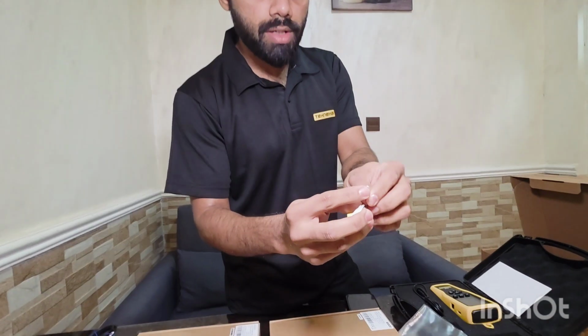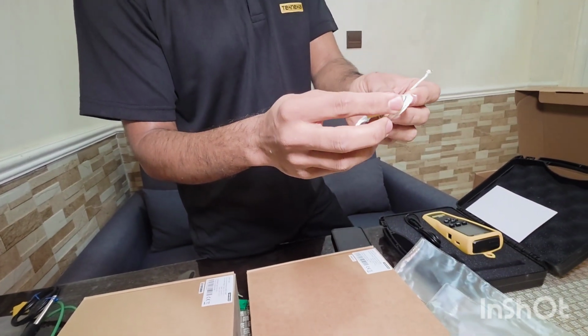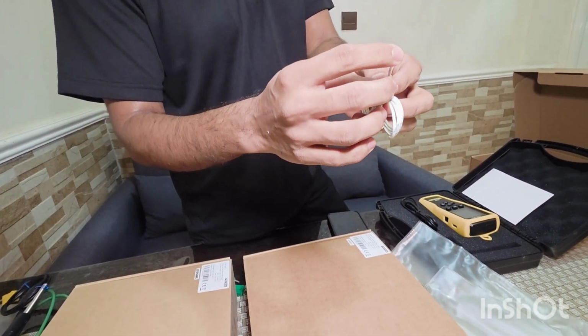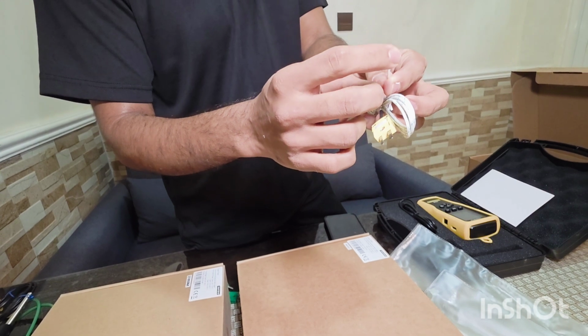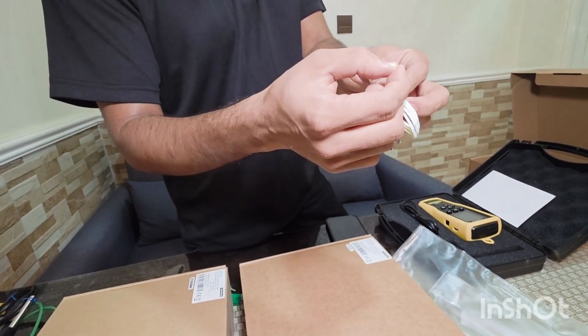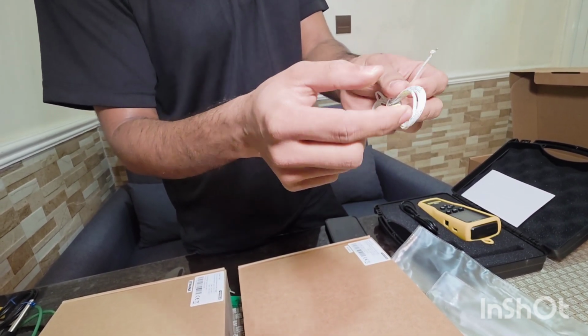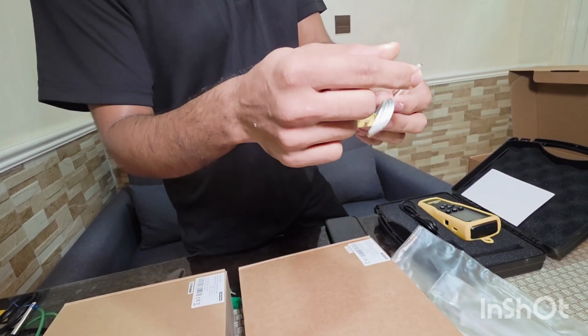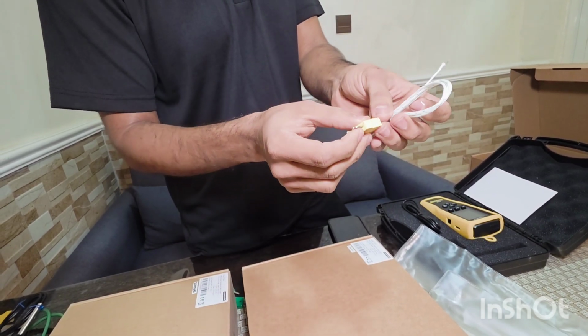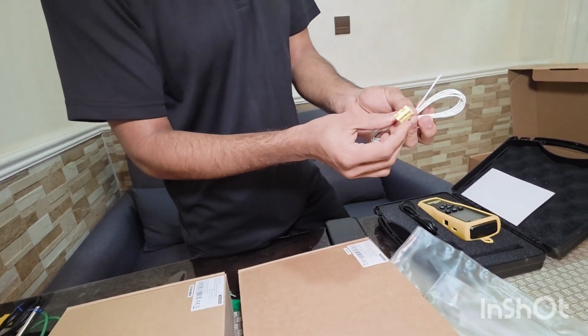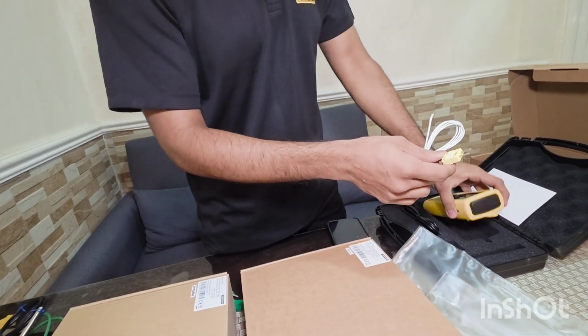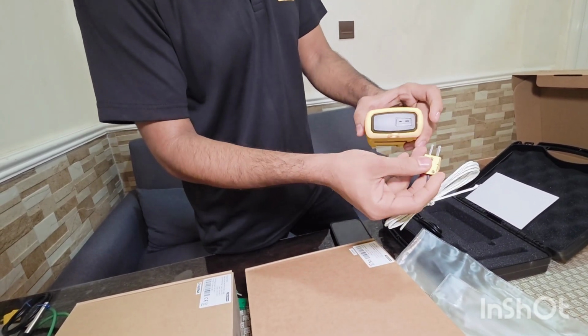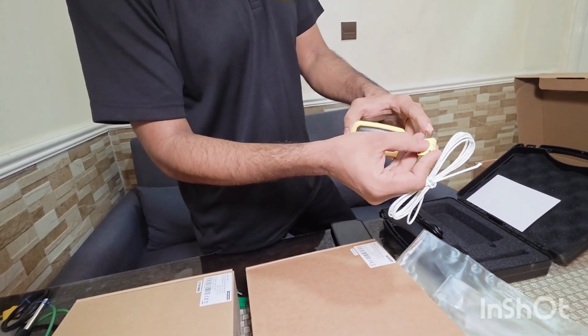All the probes are the same type K only, chromel alumel, which is this part. And as per the Seebeck effect, this is the measuring junction which we are going to measure and apply the temperature to, which is termed the hot junction. The cold junction, or reference junction, will be inside the meter. So this is chromel alumel.